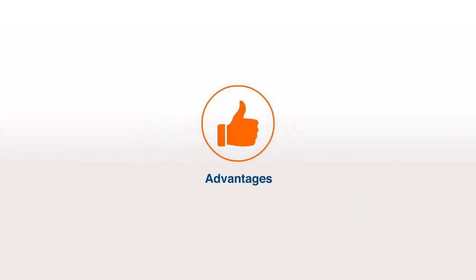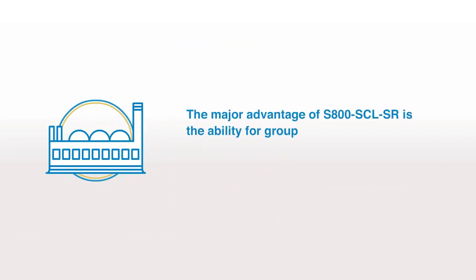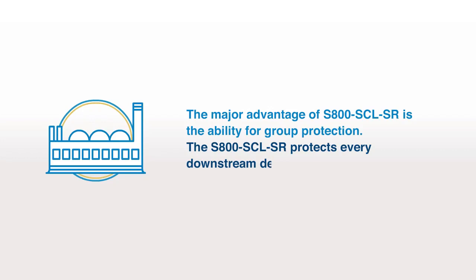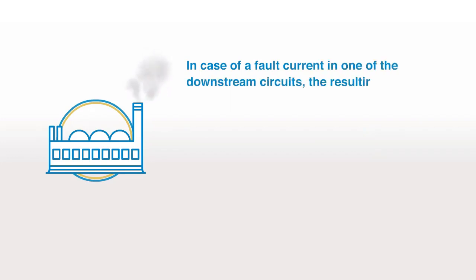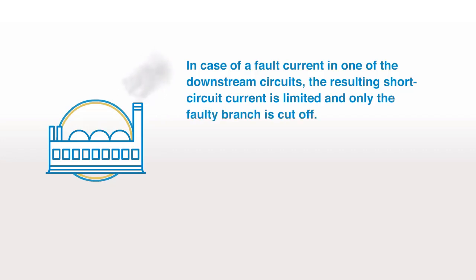Advantages. The major advantage of S800 SCL SR is the ability for group protection. The S800 SCL SR protects every downstream device up to 100 kA. In case of a fault current in one of the downstream circuits, the resulting short circuit current is limited and only the faulty branch is cut off.